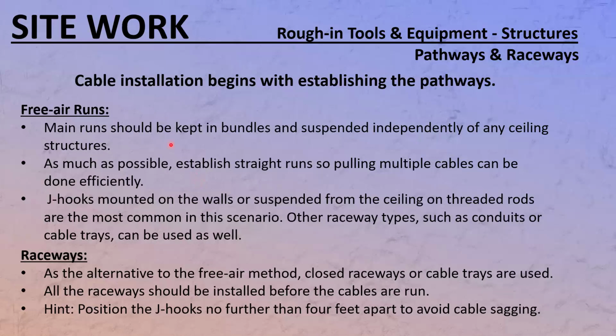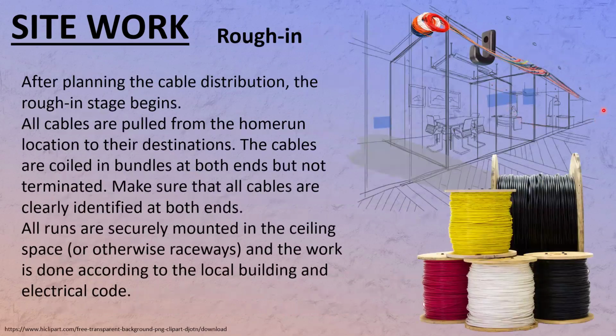So let's summarize this whole thing, just to make sure I didn't miss anything. Free air runs, main runs, should be kept in a bundle, suspended independently of any ceiling structures. As much as possible, establish straight runs so pulling multiple cables can be done efficiently. Let's say there's a LAN room somewhere here, and a bunch of rooms where a bunch of cables have to be installed to jacks, floor monuments and whatnot, in the ceiling. So you just bring it roughly to the location.